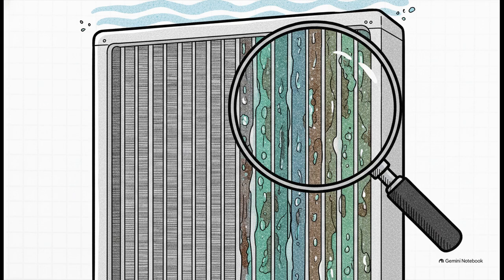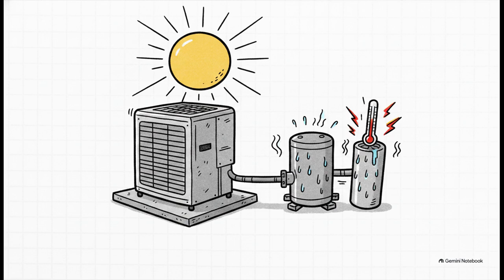If you're on the coast, you actually benefit from an added annual coil inspection right between your two standard visits. Gradual salt corrosion is just so much easier to catch and clean early than it is to try and reverse once the metal is already degrading. Conversely, if you're inland, heat is your absolute worst enemy. A unit sitting in direct sun on a concrete pad in El Cajon.